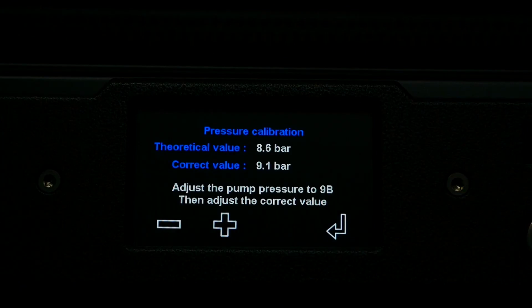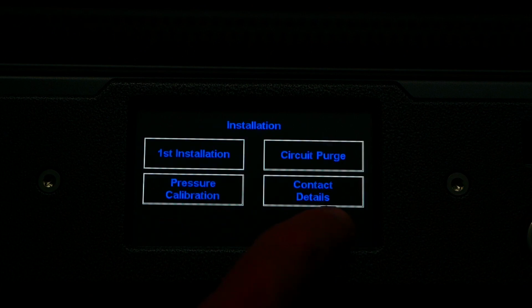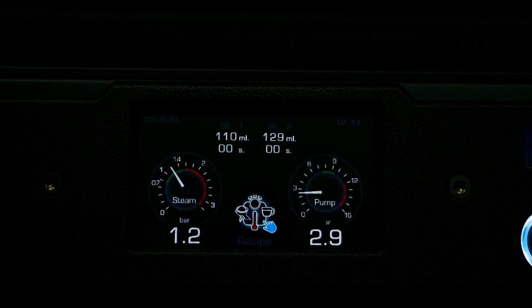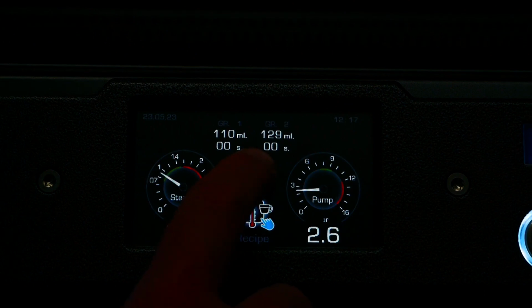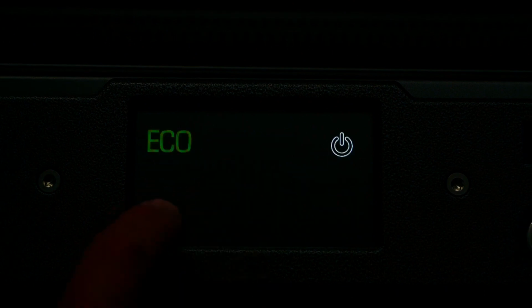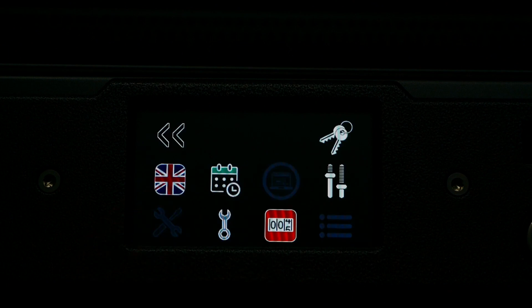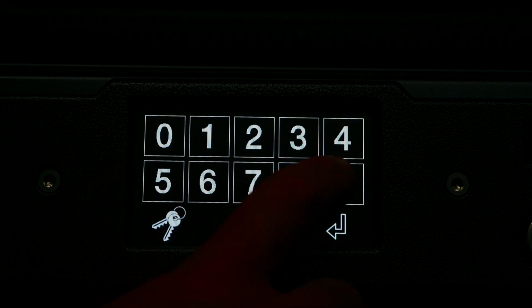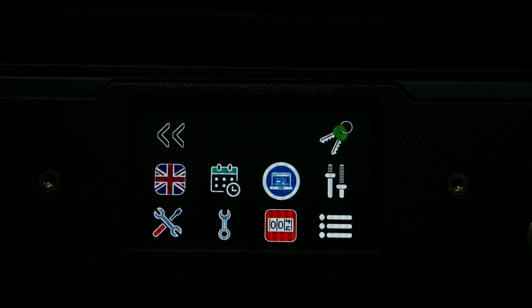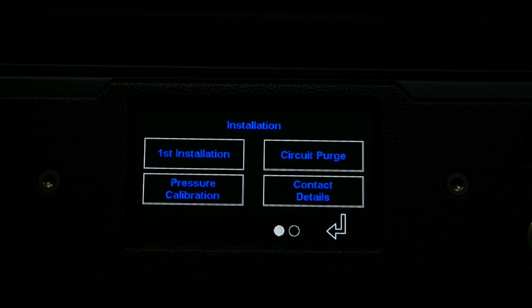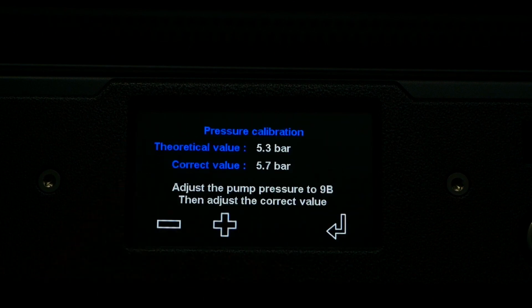The next feature to set up is the digital pressure display. With the Monte Carlo models, the physical manometers are hidden behind the group panels. We can calibrate the manometers by entering the technical menu again, by entering standby mode, hold menu, enter the password, enter the installation menu, and this time we select pressure calibration.